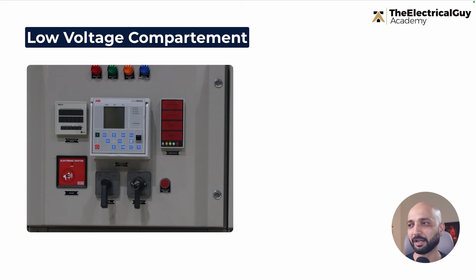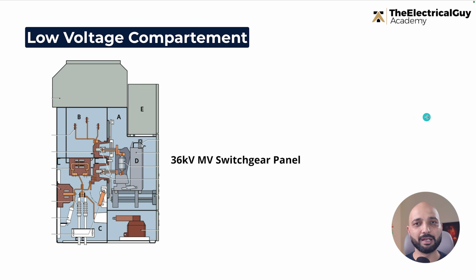Now, first, let's start with the basics. It is equally important that you understand why we call it a low voltage box, even if we use it for a high voltage or medium voltage system, right? So that's the fundamental question. Let's address that. So imagine we have a 36 kilovolt medium voltage switchgear panel. Now, of course, all across this panel, the operating voltage or the rated voltage would be 36 kilovolts. So including the cable compartment, the cable that will be entering will have 36 kilovolt.